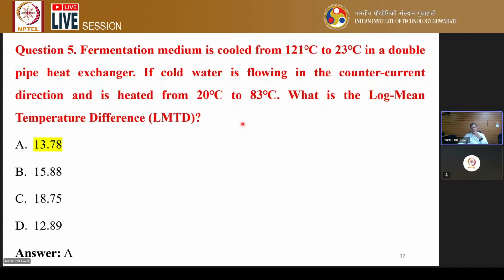We have discussed this part before. First we see the flow pattern - this is counter current, meaning the inlet of the hot stream will align with the outlet of the cold stream. The hot stream temperature decreases from 121 to 23, while the cold stream is heated from 20 to 83 degrees centigrade. In counter current flow, 121 will be at the inlet, and the 83 degrees centigrade outlet will be at the same end as that inlet.